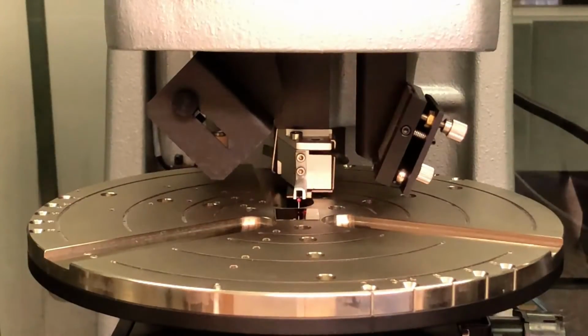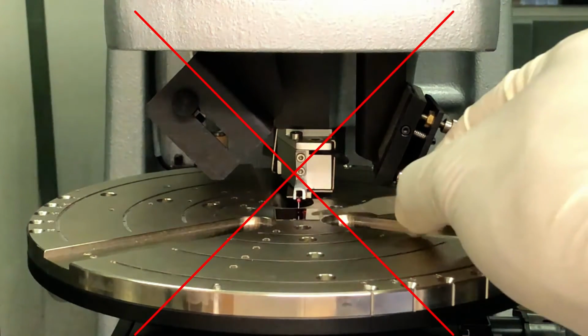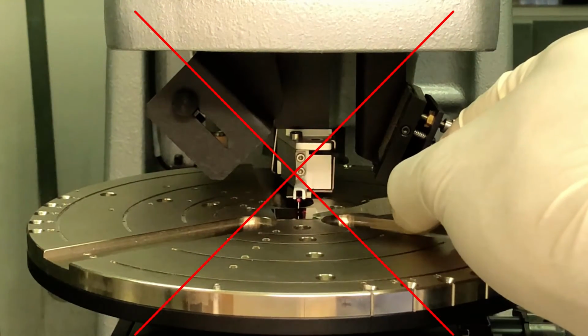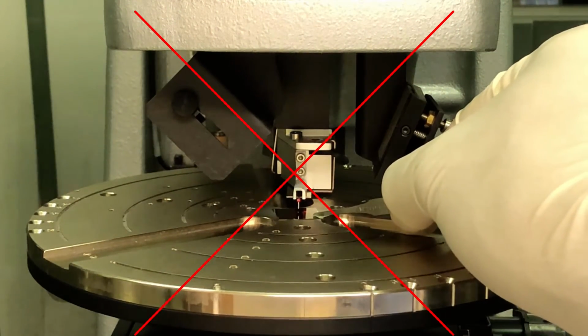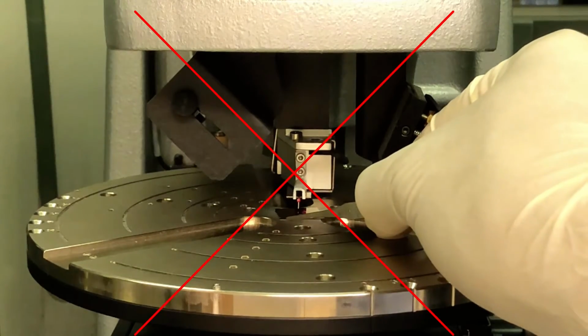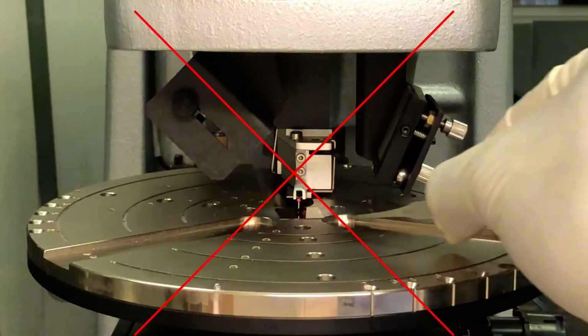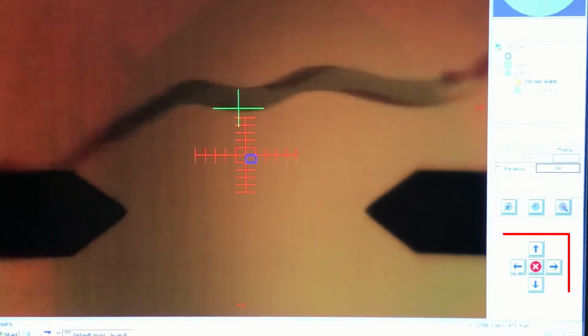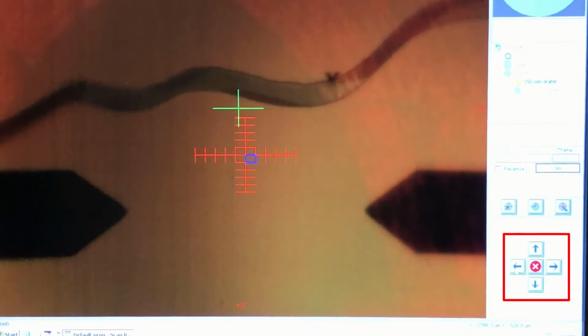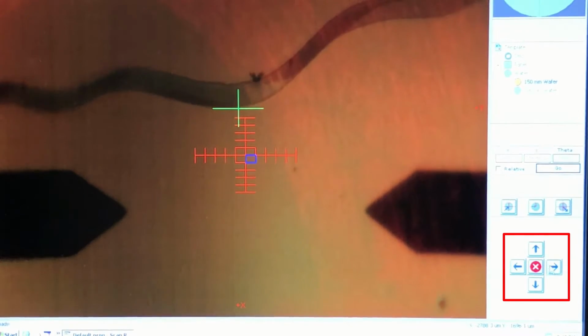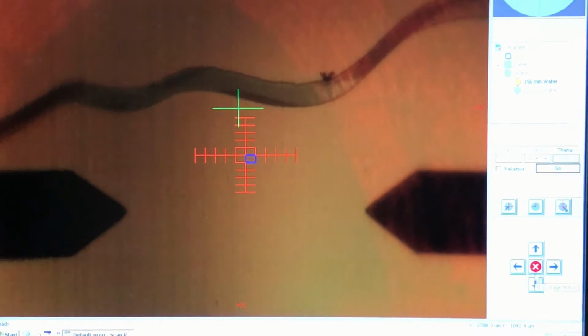It will be easier to see the approach from the screen. This way you can clearly see when the probe is in position. It's likely that the sample position needs to be adjusted, but I would caution against moving the sample manually. You are more likely to bump against the probe tip and damage it with the sample or tweezers. Instead, use the arrows located on the bottom right corner of the user interface to move the sample into position.